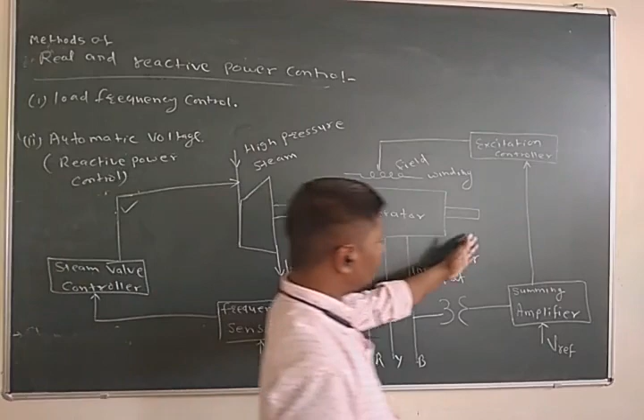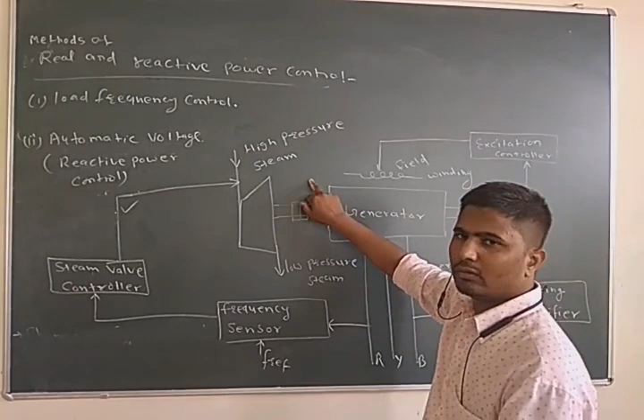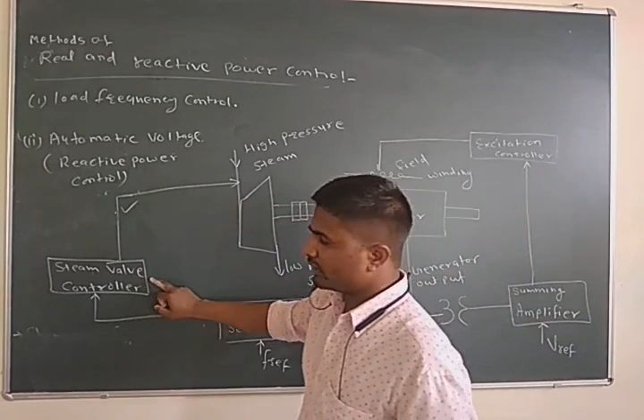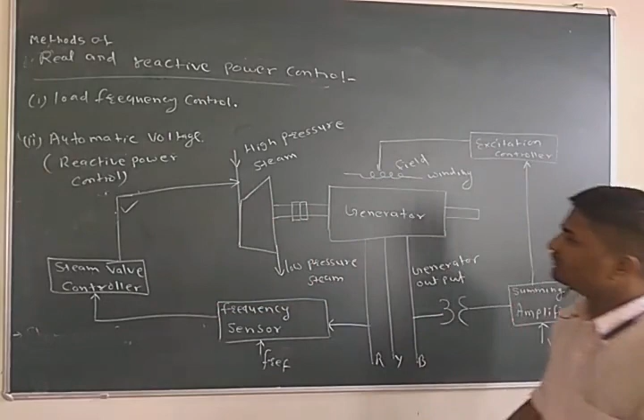Now this complete system shows the active and reactive power control of our power system. So in this system there is a generator. A generator input is provided connected to the turbine and output of generator is given to the system, and this is the excitation system. So here to control the active power of our system we use steam governor controller. And similarly to control the reactive power output of generator we use excitation controller.